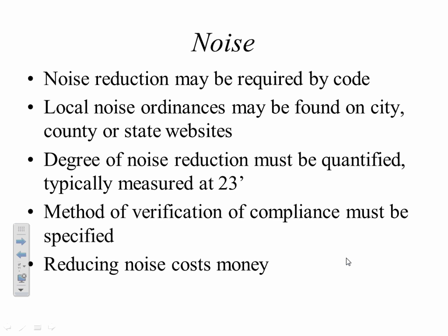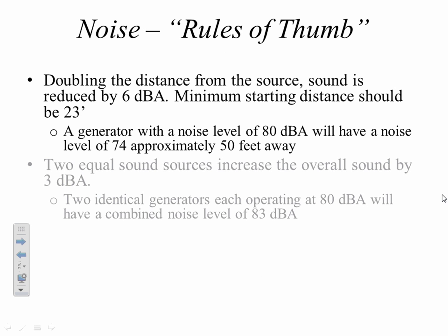The noise reduction may be required by city code, it usually is. And for whatever reason, they've chosen 7 meters or 23 feet as the distance that they want to start measuring at. And a good specification will require that a noise reduction must be quantified. In other words, let's talk about 70 dBA at 23 feet, and then everybody should know what's being discussed. Reducing noise does cost money, big money.